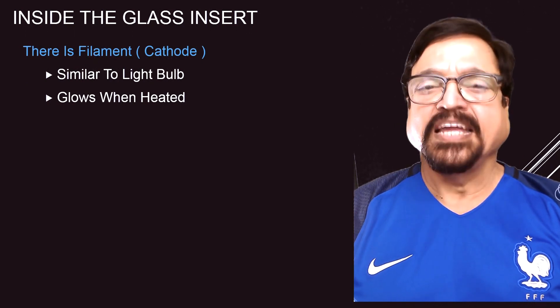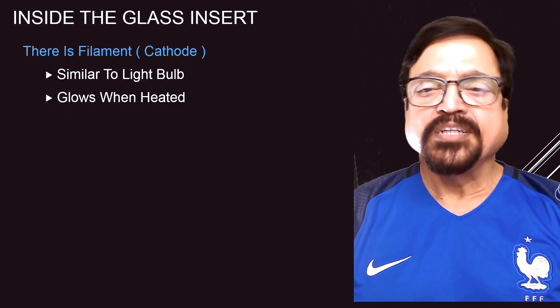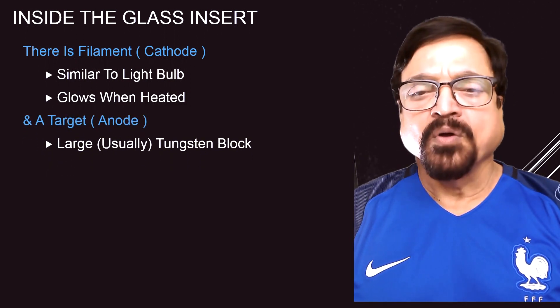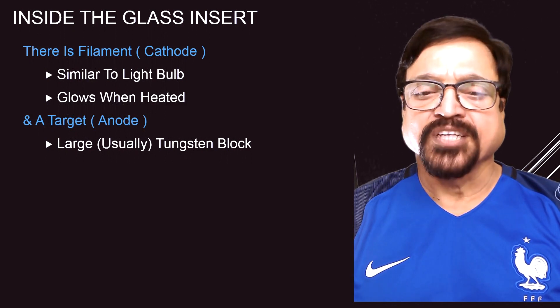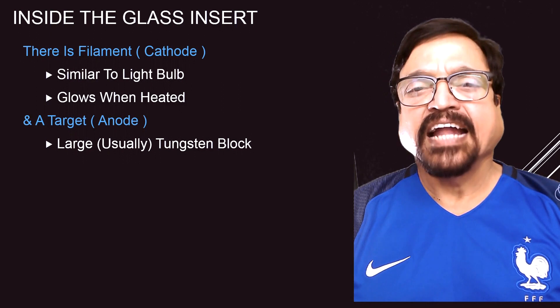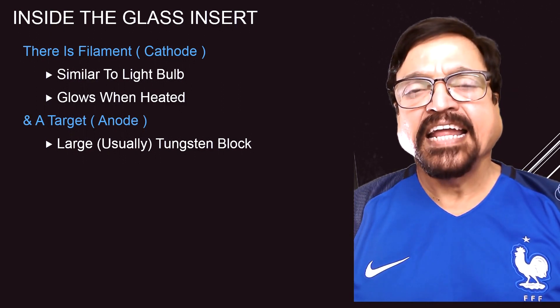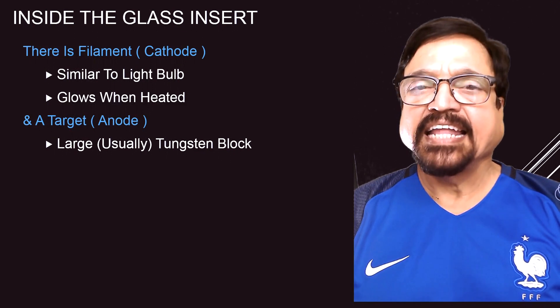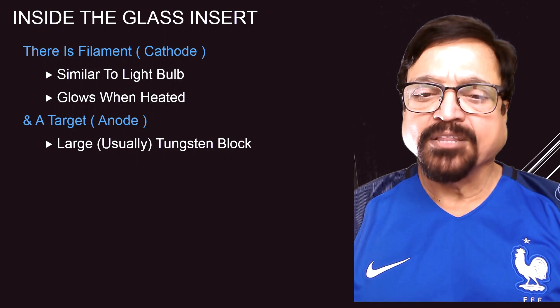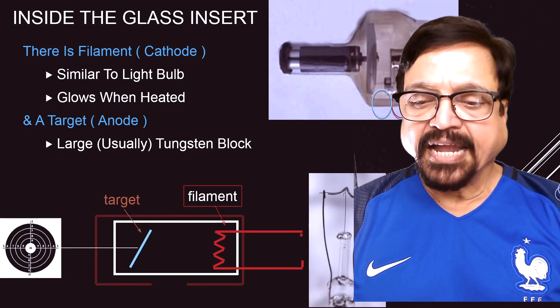Now let's briefly see what the other structures are. There is a cathode which is similar to a bulb — it glows when heated and emits an electron cloud by a thermionic emission process. This electron cloud is accelerated by the potential difference and attracted towards the anode. From there, the accelerated electrons get decelerated and are converted into X-rays. So what we have here is a filament cathode and a target anode.